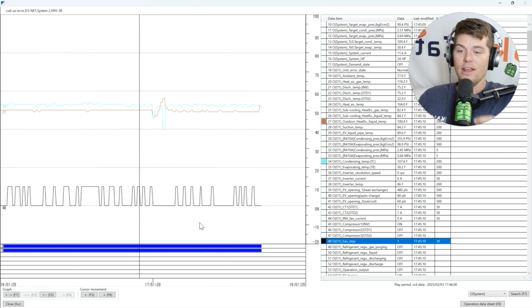I need to go look at indoor valve pulses. I need to go look at the subcooling circuit. I need to go look at the accumulator. I need to go look at the submodule, right? I need to go look at the discharge temps. This is where it's going to point you. It's a compass. So use it as a compass, not as an anchor, right?